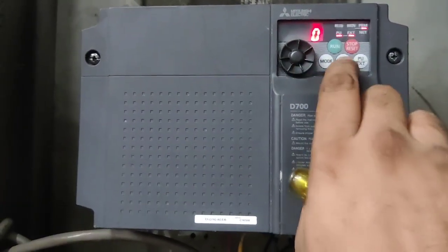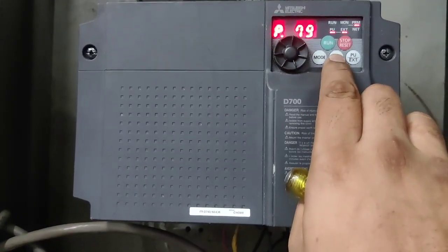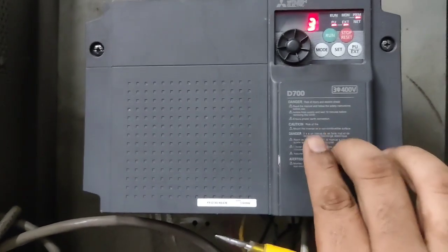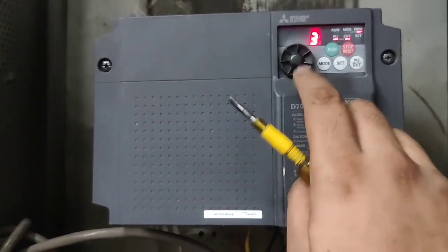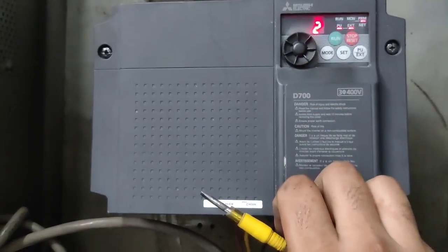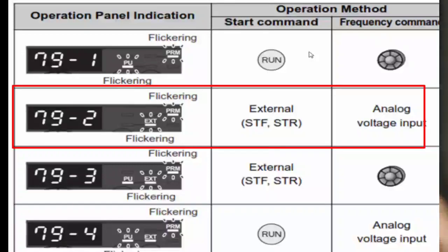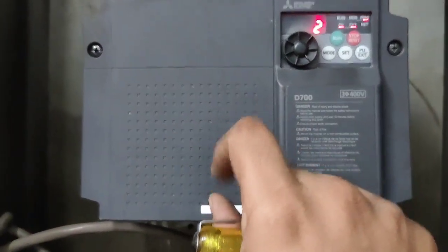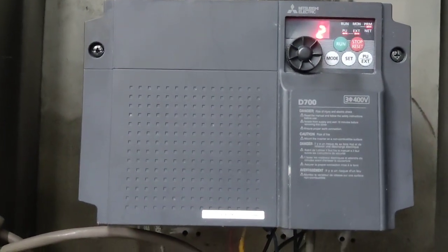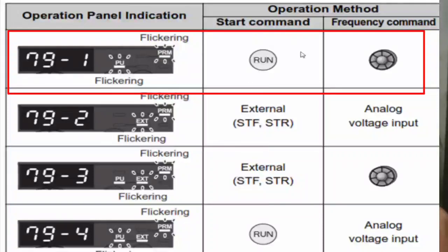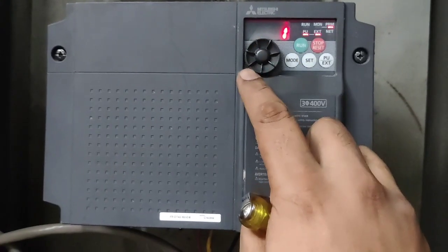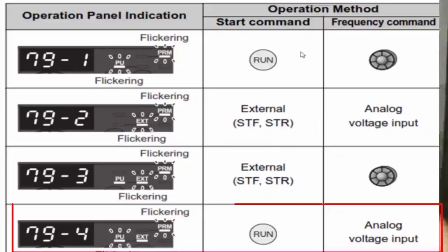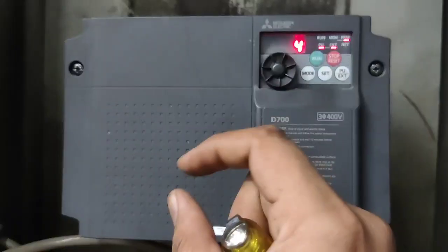Next parameter is P79, which is operation mode selection. If you set 3, your drive will start with an external push button and speed control will use the PU port. If you set 2, your drive will start and stop with an external push button and frequency will be changed with an external potentiometer — external mode. If you set 1, your drive will start and stop with PU mode push buttons and speed will be controlled with the PU potentiometer. If you set 4, your drive will start and stop with PU mode and speed will be controlled with the external potentiometer.